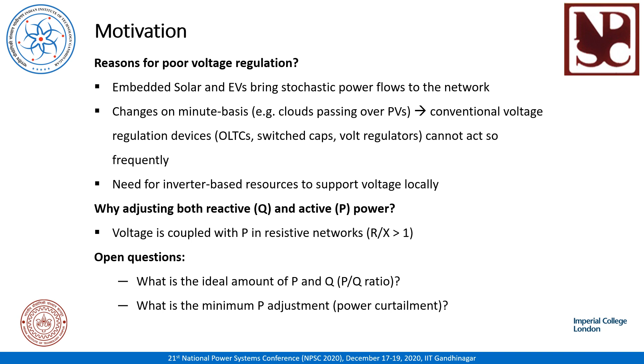Now, why adjust both active and reactive power to regulate the voltage? Because for a weak grid where R by X ratio is more than 1, the voltage is coupled with reactive as well as the active power. Therefore, the questions are: what is the ideal amount of P and Q to obtain the maximum voltage regulation, and what is the minimum P adjustment, because curtailment of P should be right to avoid the loss in revenue.